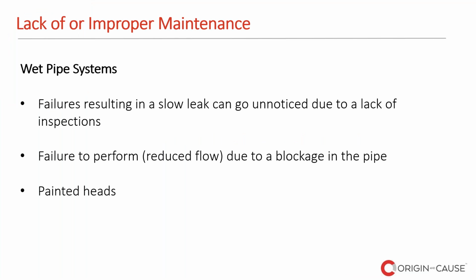And when it comes to failures resulting from a slow leak that can go unnoticed, it's a little bit more of an involved investigation because trying to find out when that leak started can be a little difficult, but it's not impossible. There's also an issue of a failure to perform. So if a system is rated to cover a specific area in that building, and there is a reduced flow due to a number of things, either a blockage in the pipe or something else, like valves not properly open or valves not properly functioning, then obviously all of that goes back to maintenance, and we can trace that back and find out who was supposed to be doing that.